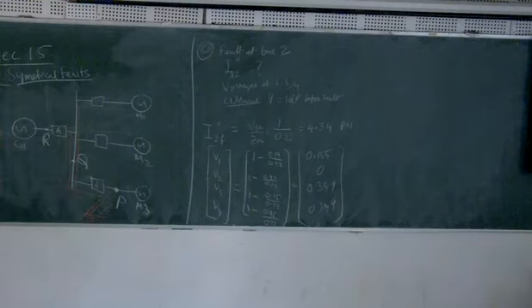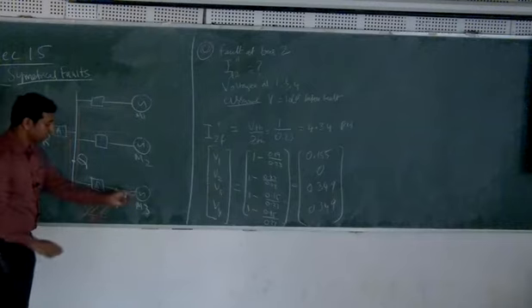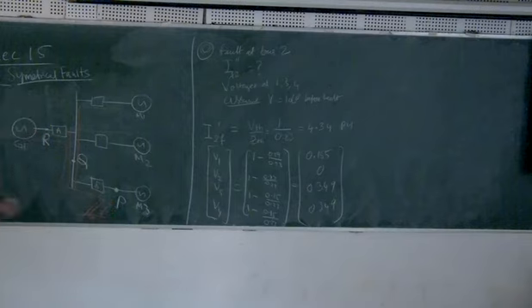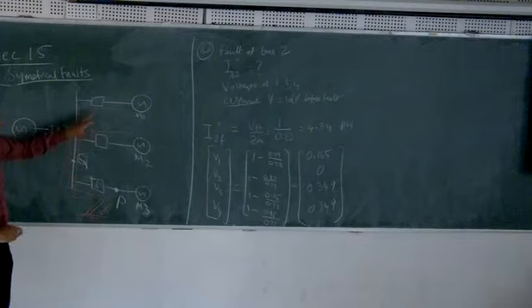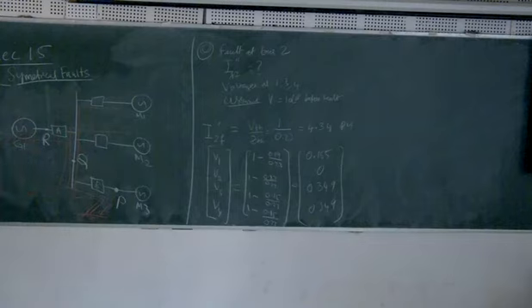Now, if you look at circuit breaker B, it is looking at three fault currents. There is another fault current directly from this, so that's also there. Because of its location, B is looking at three fault currents, whereas circuit breaker A is only looking at this fault current, and this circuit breaker only at this fault current. Now, you have to coordinate the design of these circuit breakers. There is a fault current here, here, and here. All three of them are looking at the fault current.